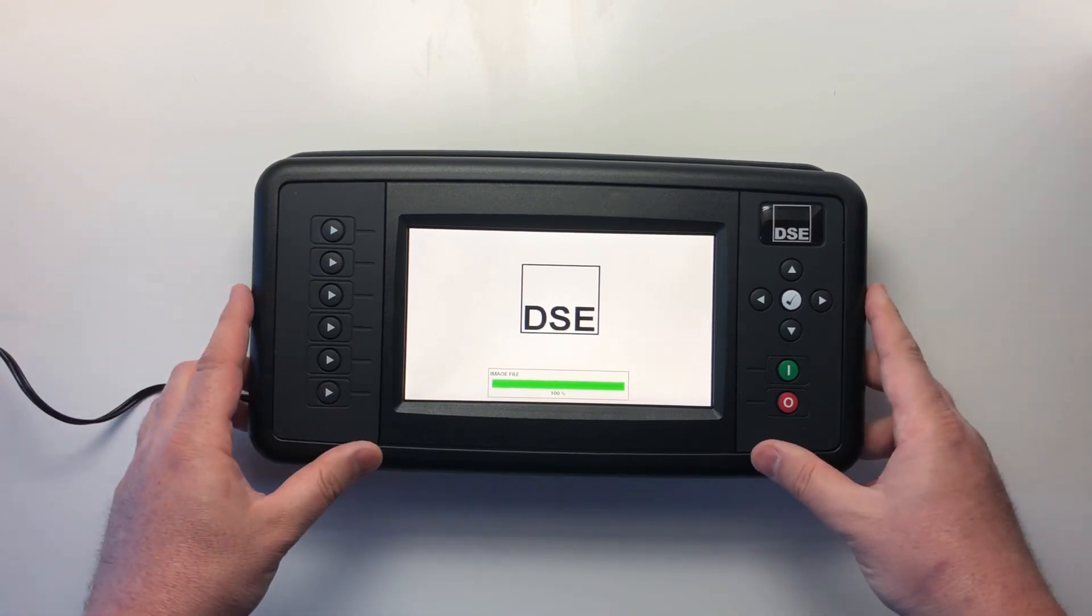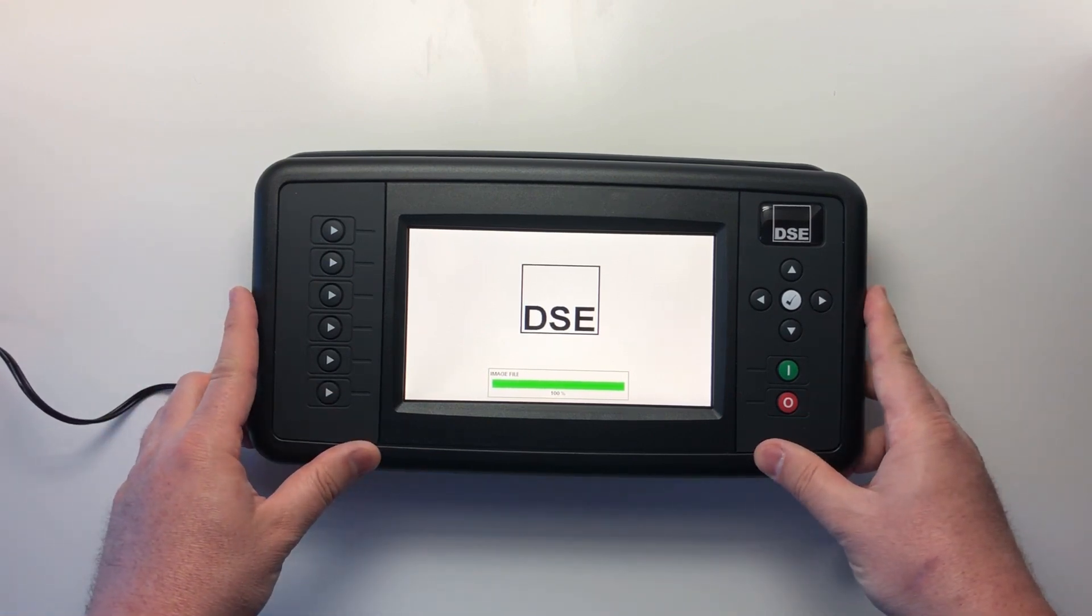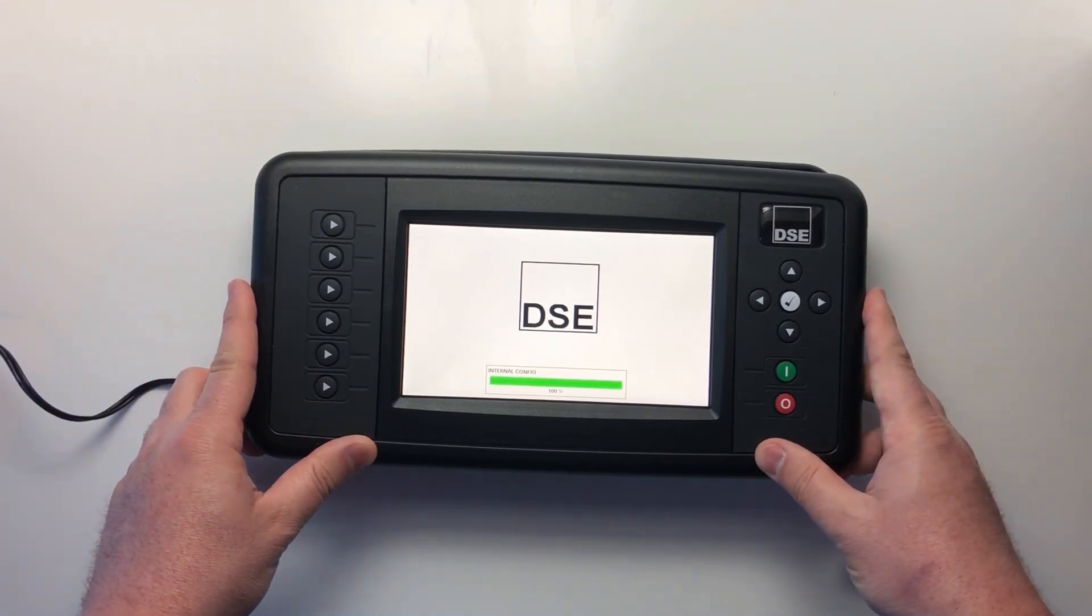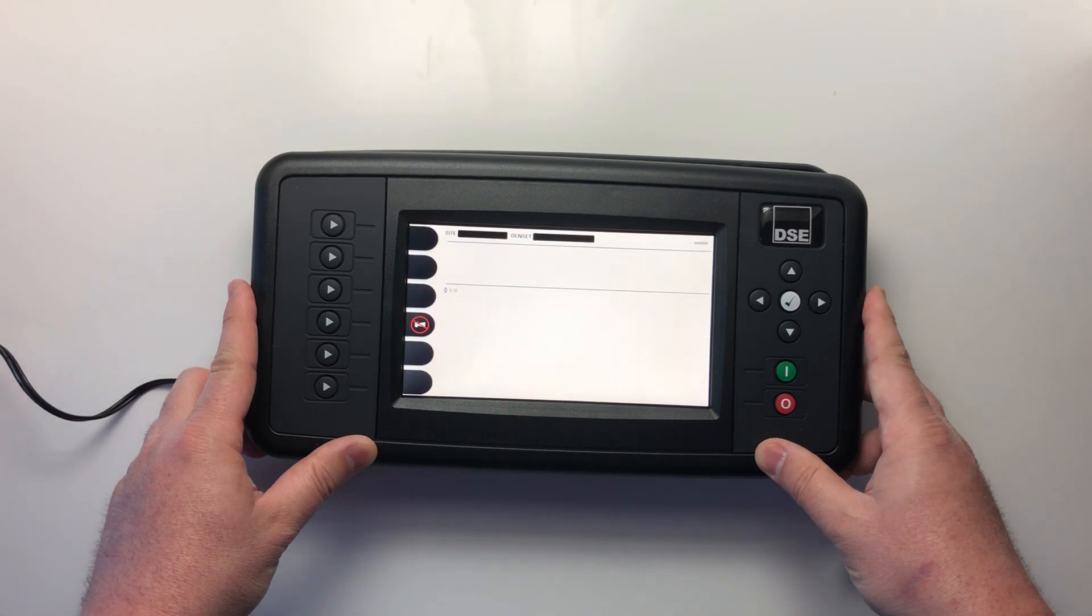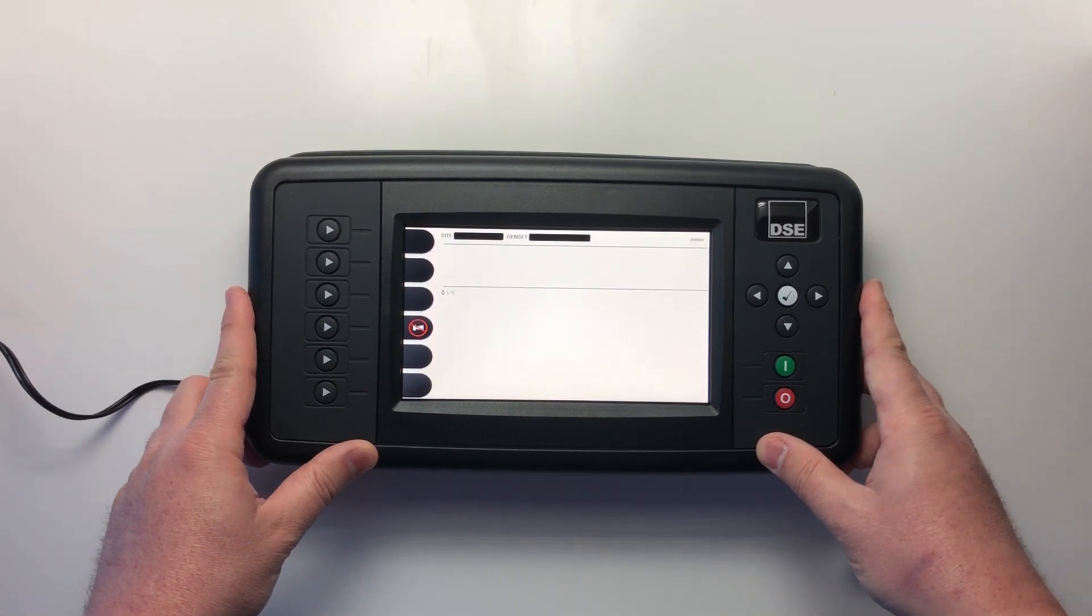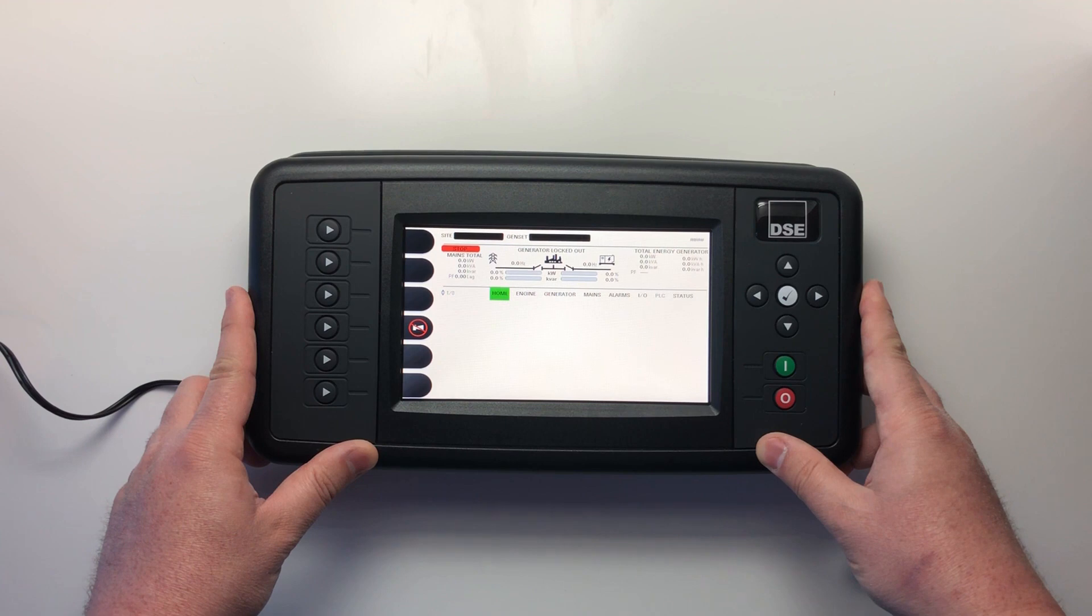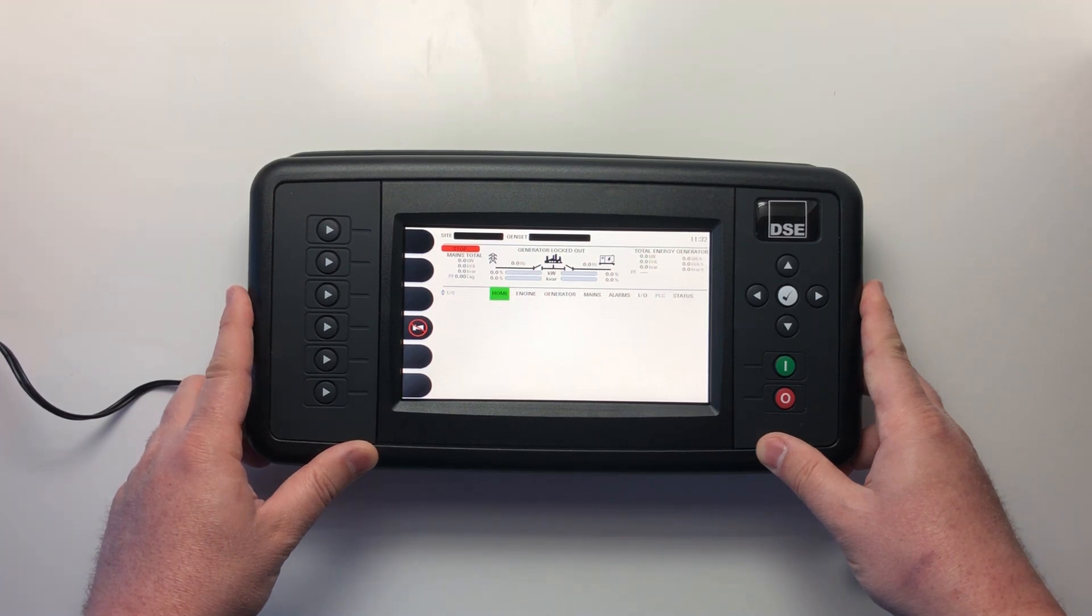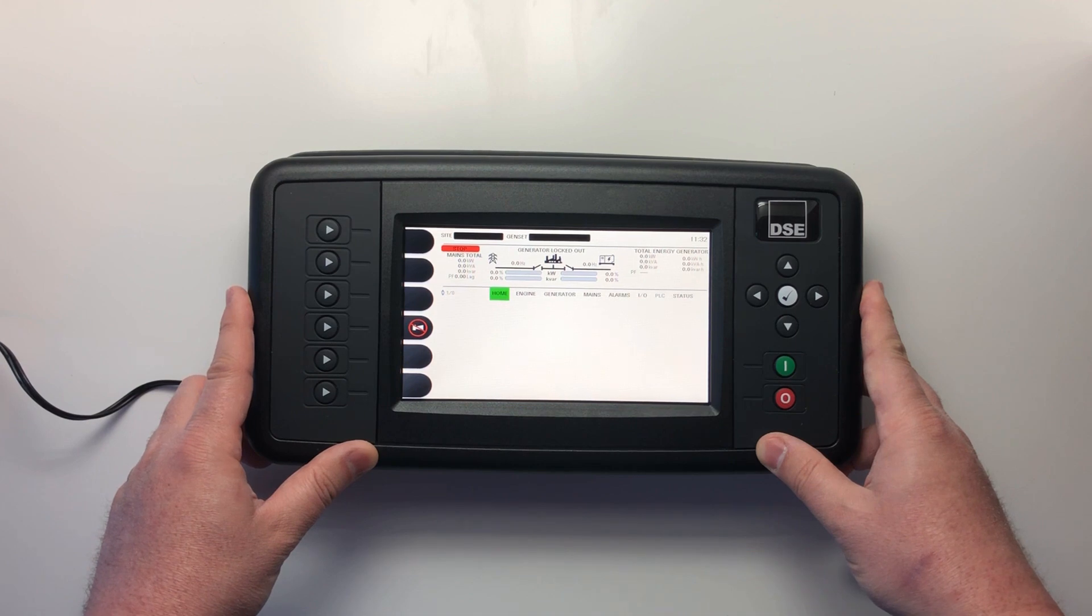The DSE8920 supports both isochronous and droop modes for kilowatt and kVar sharing. The module also offers an internal PLC logic, which gives advanced flexibility for monitoring and controlling different accessories and assets on site.